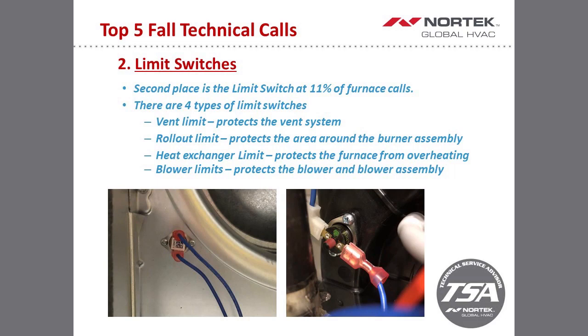So the vent limit basically will protect your flue piping, making sure that doesn't get too hot. Your rollout will protect the area in regards to the burner manifold if we potentially have a cracked heat exchanger. Also, if we have soot in the heat exchanger from not converting a furnace over, that will apply to your rollout limit. What I would just remind you guys is that the rollout and the vent limit are manual reset. So if those were to trip, you have to hit the button on the limit in order to reset that limit switch.